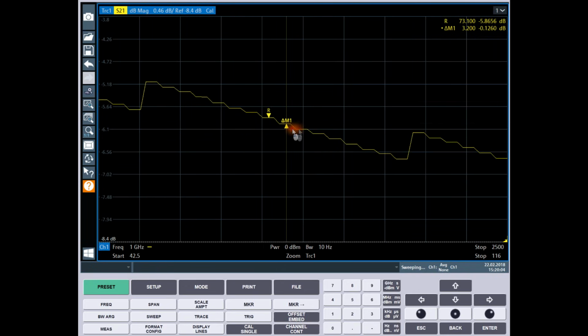Let's measure the next one, put that one over here, and put this one right next to it. And you can see this one is 0.1074. So these attenuators are not exactly the same step each time. And that makes sense because there is some repeatability limitation. Now, this is not because of the instrument. In fact, the network analyzer is revealing the imperfections of the attenuator.